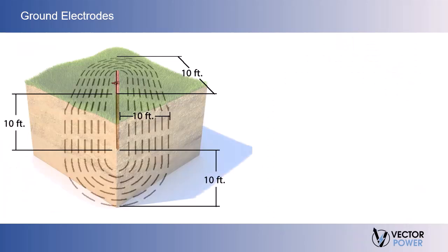The electrode can be considered surrounded by concentric shells of earth or soil, all the same thickness. The closer the shell is to the electrode, the smaller its surface, hence the greater its resistance. The further away the shell is from the electrode, the greater the surface area, hence the lower the resistance.